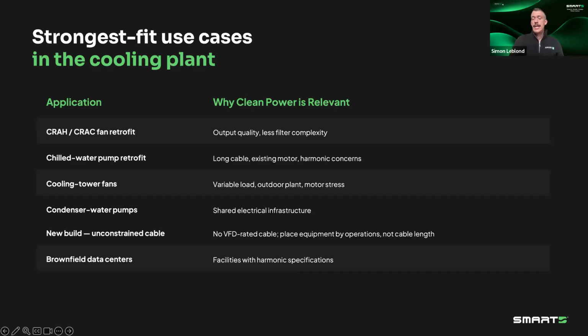retrofit, if you have an existing facility and for any reason you have places where you're not running VFDs and you maybe don't have the right cable type or you don't have the right motor type, they're not inverter duty, that becomes an easy energy efficiency win by plugging in the Clean Power VFD and you're ensuring that the motor really still sees a sine wave even with the variable speed control.